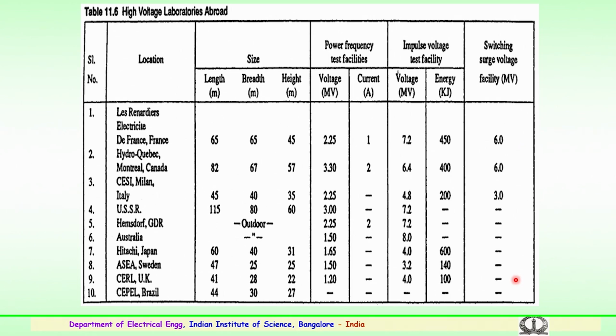Some of the high voltage laboratories, which have various sizes for power frequency, impulse and switching surges, are available in several parts of the globe. A few examples are here. In France you have a laboratory size of 65 meters by 65 by 45 meters height, where the facilities include power frequency of 2.25 million volts with a current rating of 1 amp, an impulse test facility of 7.2 million volts and energy of 450 kilojoules, and a switching surge facility of 6 million volts. Similarly, laboratories are available in Hydro-Quebec, Canada, CESI, Italy, in USSR, Australia, Japan, Sweden, UK, Brazil. These are the values of the sizes of the laboratories.